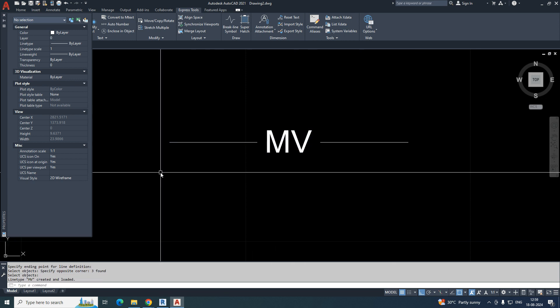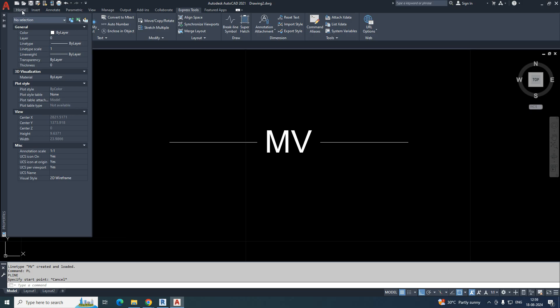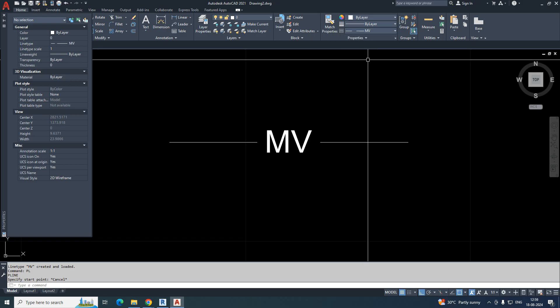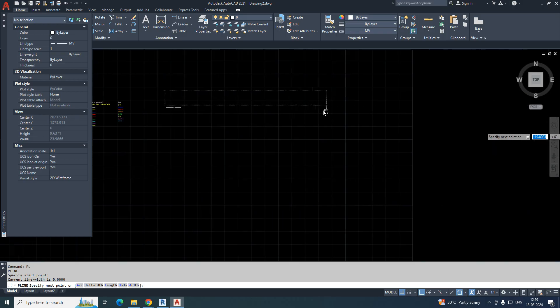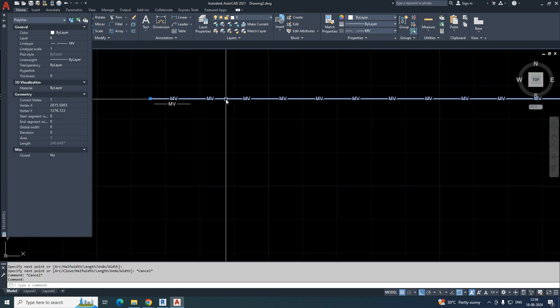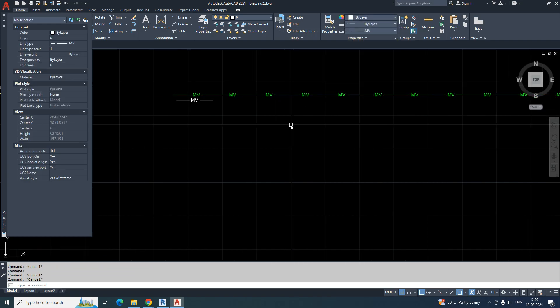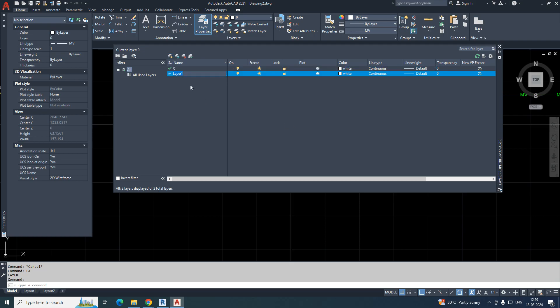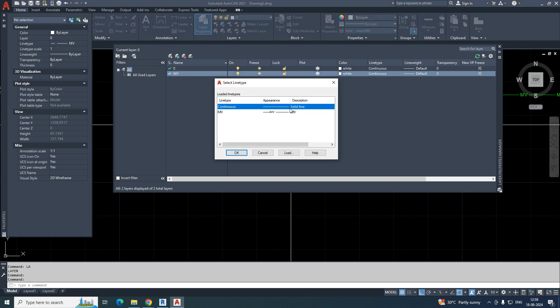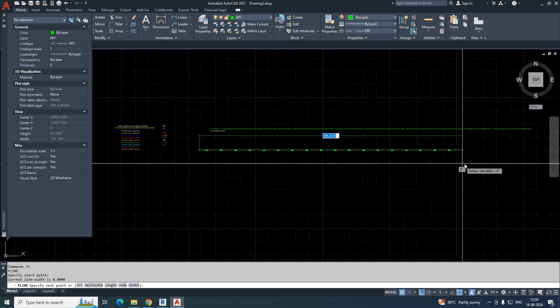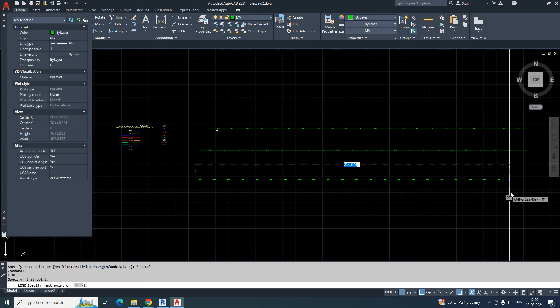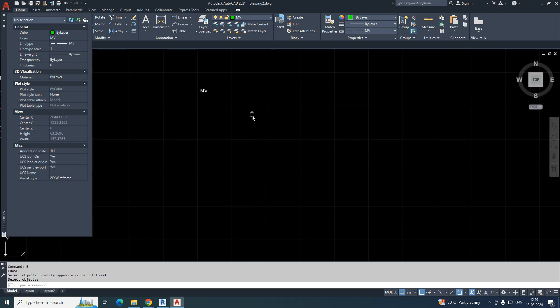They will ask for the starting point and end point — select the area you need and press Enter. Then draw a line or polyline. Once you draw the line, the MV text will appear along the line automatically. You can also go to the Layer Manager, create a new layer called 'mv,' set it current, choose your color, and then draw a polyline — it will appear automatically with that line type.